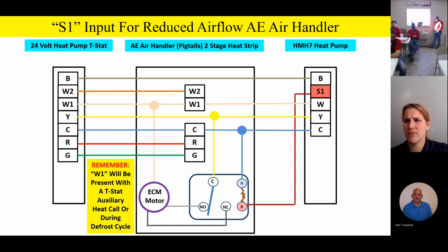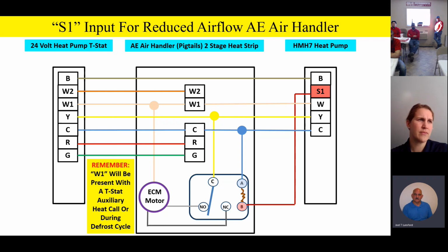So it's bypassing that kit that comes with for the ECM motor. I kind of like the way you think there. That's exactly, electrically and mechanically, what's happening. So anytime basically we get a W call, either from the outdoor unit going into defrost or the indoor unit or the thermostat calling for auxiliary heat, it's going to drive that ECM motor to 100%, so we don't overheat the heat strip. Yeah. Good questions. Any other good questions or comments? Everybody good? Have customers complained about the ramping up and down of the blower motor during heat operation?